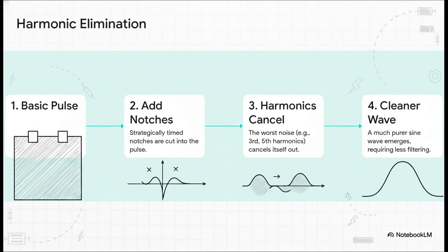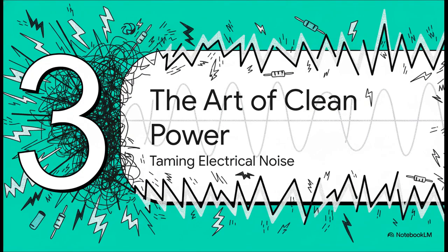Instead of one big, dumb pulse, the engineers chop it up with these strategically placed, precisely timed notches. By controlling the exact width and position of these new pulses, they can actually cause the most troublesome harmonics to literally cancel themselves out. You're not filtering the noise, you're shaping the waves so the noise is never strongly generated in the first place. It is the electrical equivalent of preventative medicine, and it's what allows for incredibly efficient and clean power.